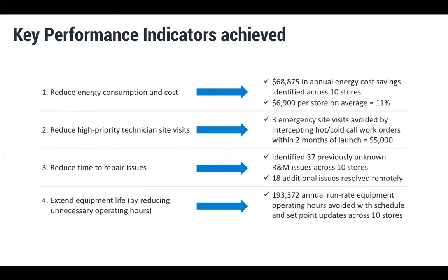Reduced time to repair issues. There were 37 previously unknown repair and maintenance issues across the 10 stores. Actually, that was only across 9 of them, because one of them just recently came on. And then 18 other issues that were resolved remotely, largely related to improperly configured schedules as we found them. But a few other things too, some control sequence problems that we were able to use the Switch platform to override.